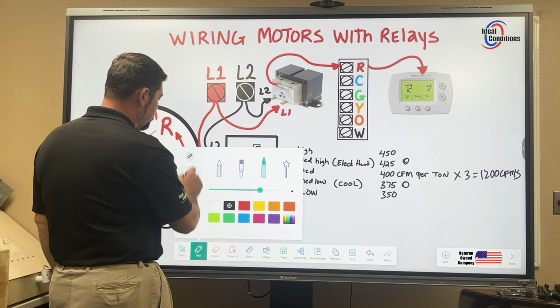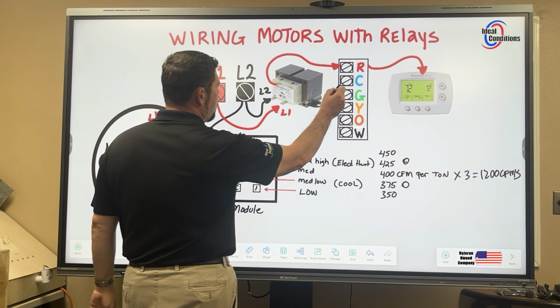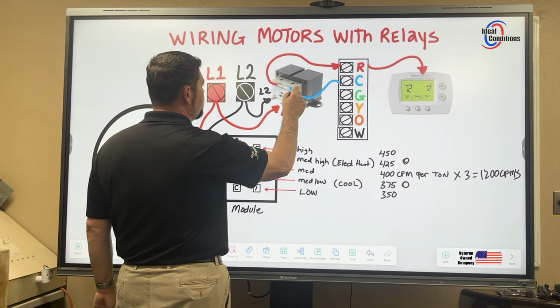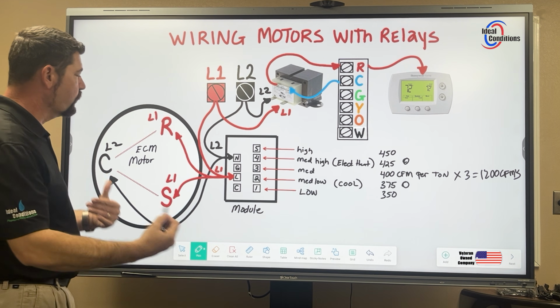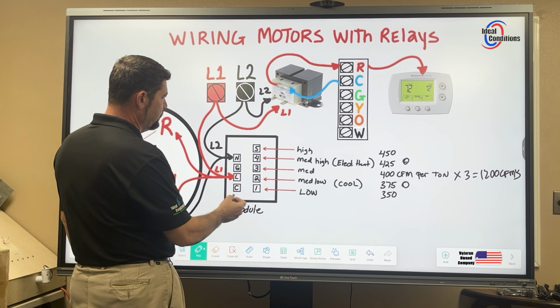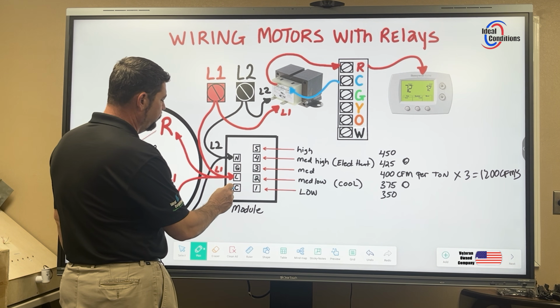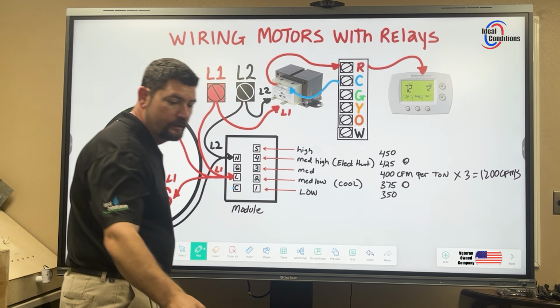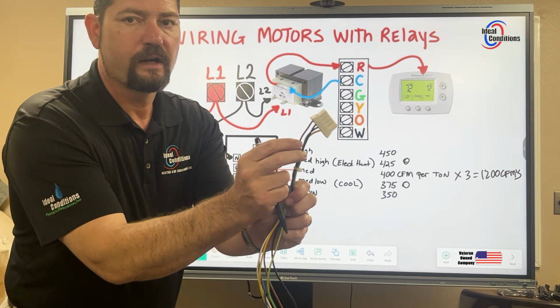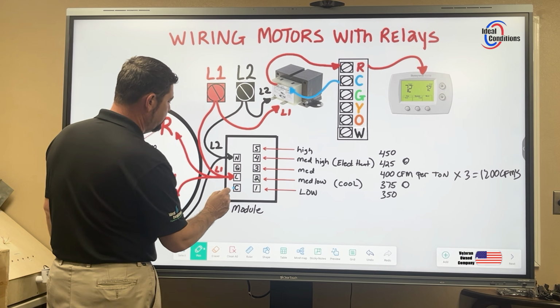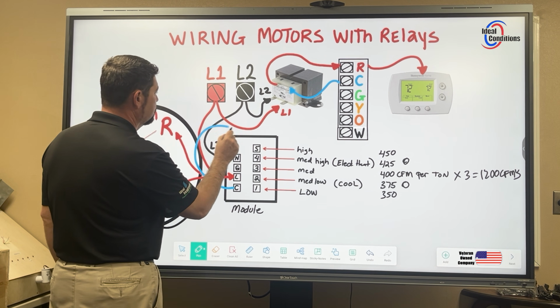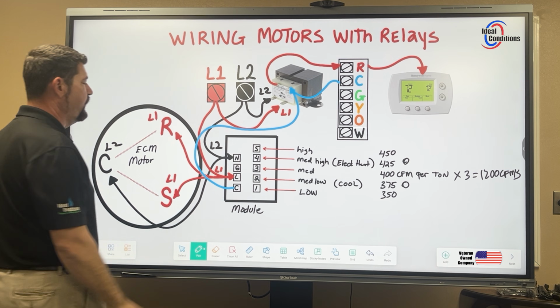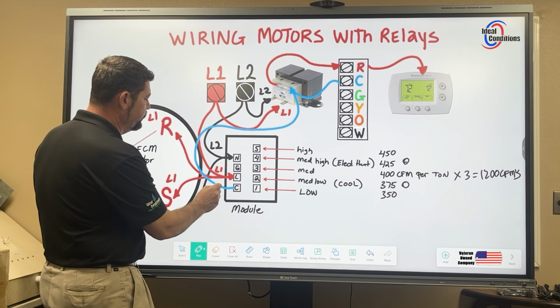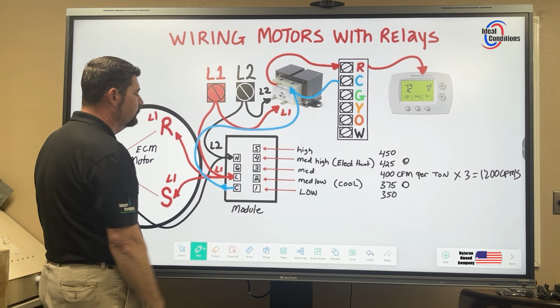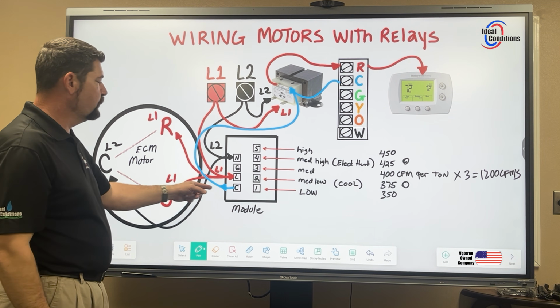We're going to go ahead and just switch some colors up. Common has to come back. So we're just going to put our common right back here on our transformer. While we're on common, before I change any colors up, I'm going to say that common needs to come from the motor, which is typically the brown wire that's on the plug. This is our low voltage common that I'm talking about. So this common here will come up and just give a path back to the transformer. So this common is an output. I'm going to put my little output arrow. So we have input, input. This is low voltage output.